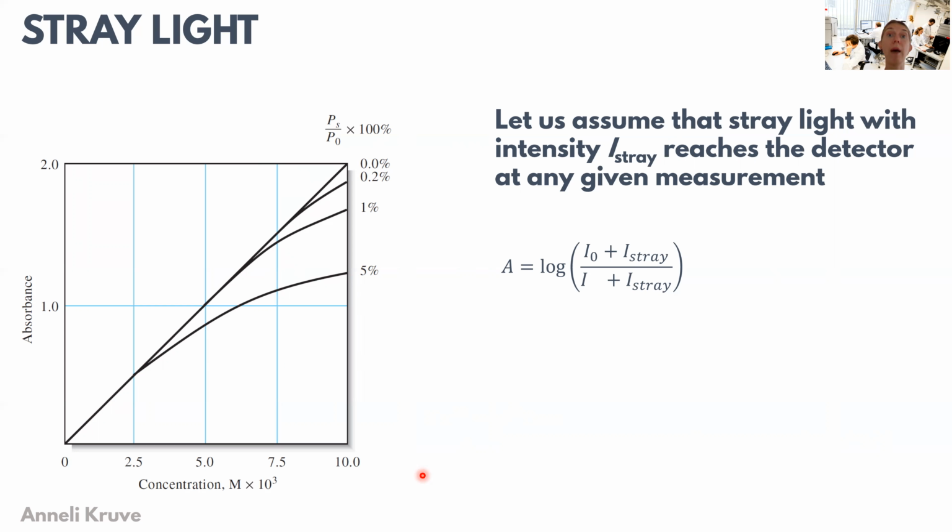And many instruments have an automatic switch that blocks the light that could come from the environment from going to the detector, but some don't. And in these instruments, it's important that the light from the environment does not go to the detector, because that can make our detector a bit blind. So it is hit by too many photons at a time, and it becomes less sensitive.